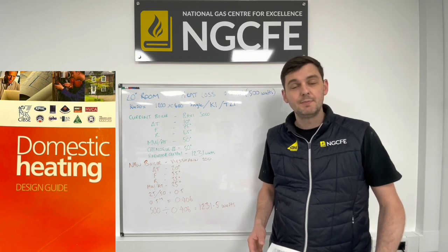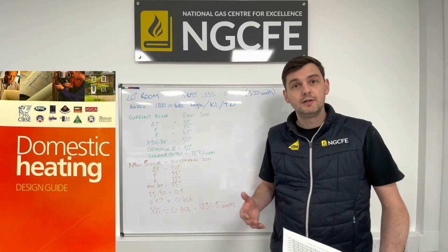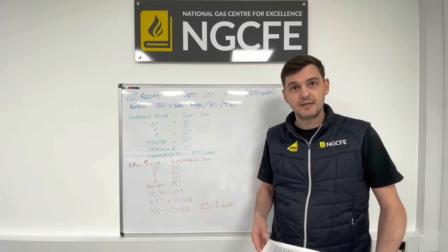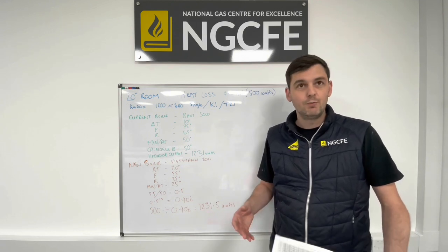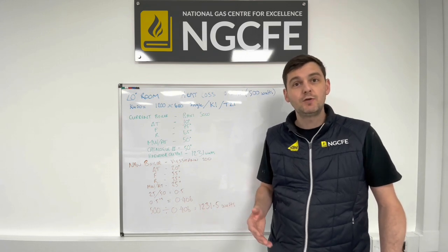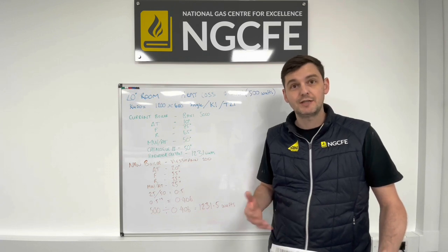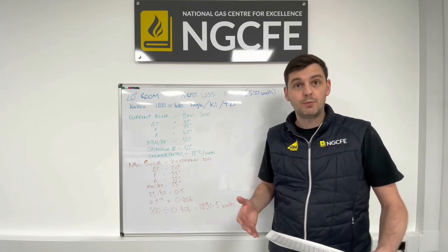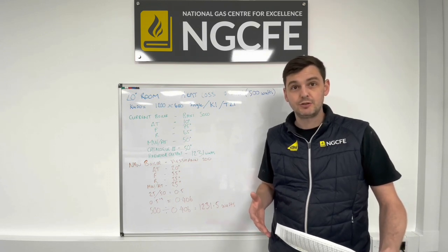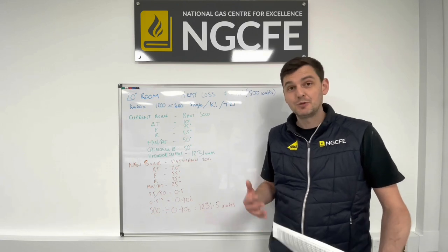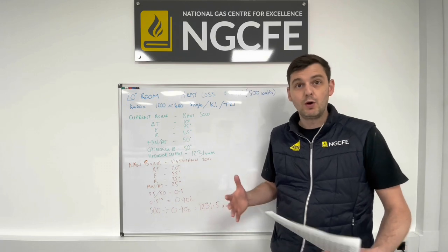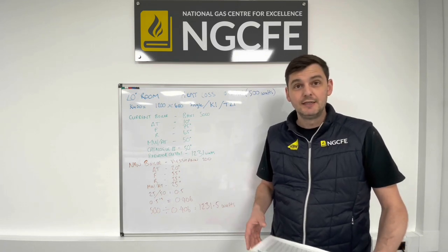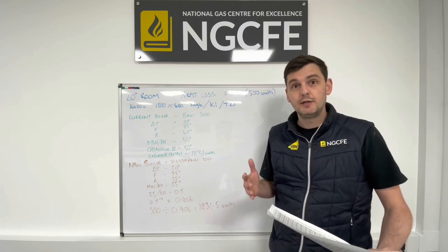Today's video from NGCFE is a follow-on from a recent video we did on the new Part L regulations coming in on 15th June. Some of the questions we've had back are around radiator sizing — is it going to be as big an issue as we think? The short answer is no, because we've had a history over the last 20 years of engineers oversizing radiators based on aesthetics. We'll find that a lot of radiators already in properties will be adequate for 55-degree flow temperatures. We've selected a radiator we commonly see in rooms as our example.